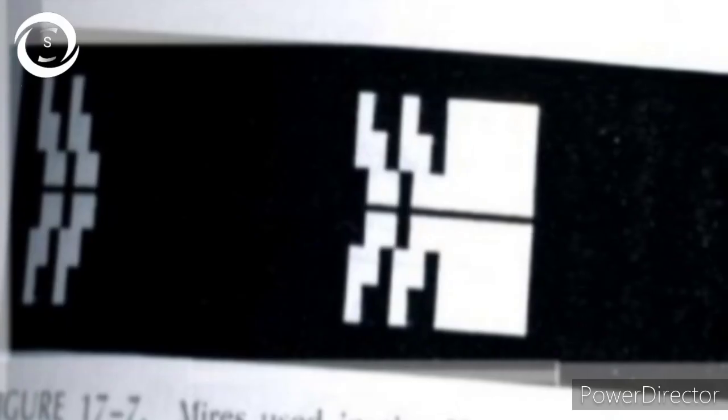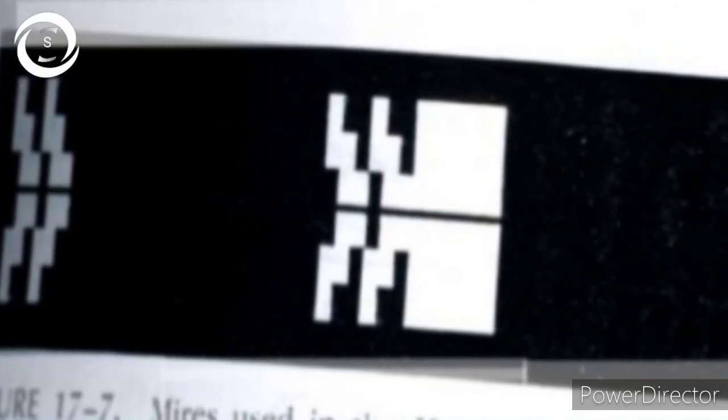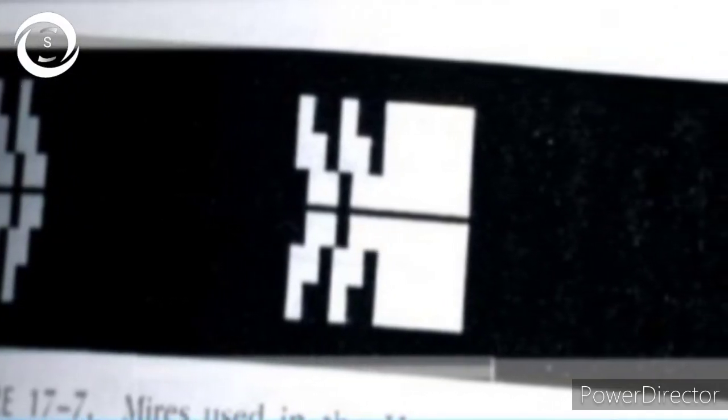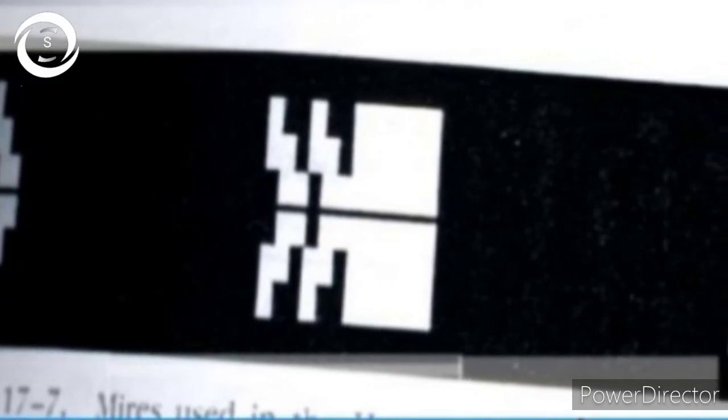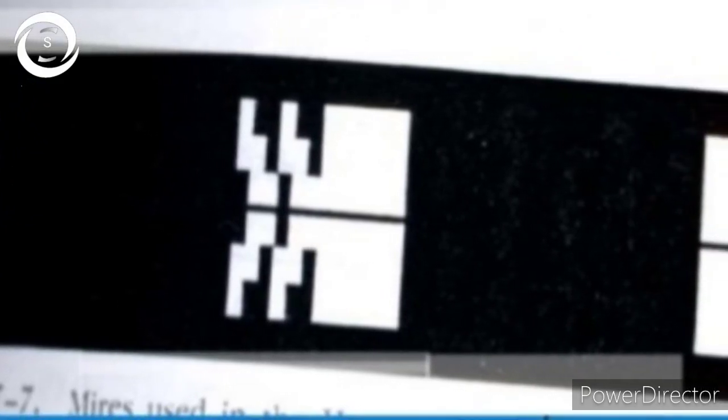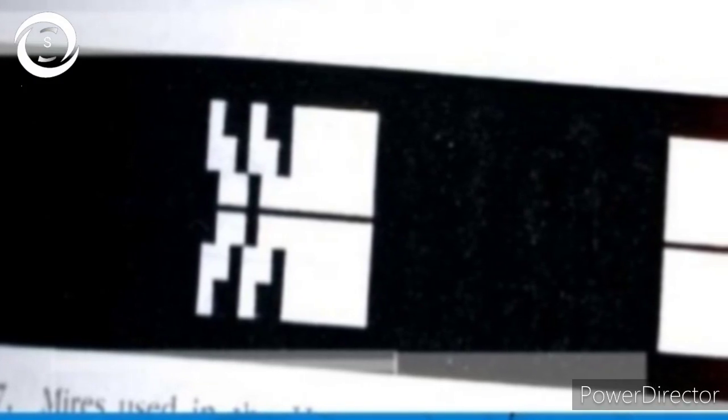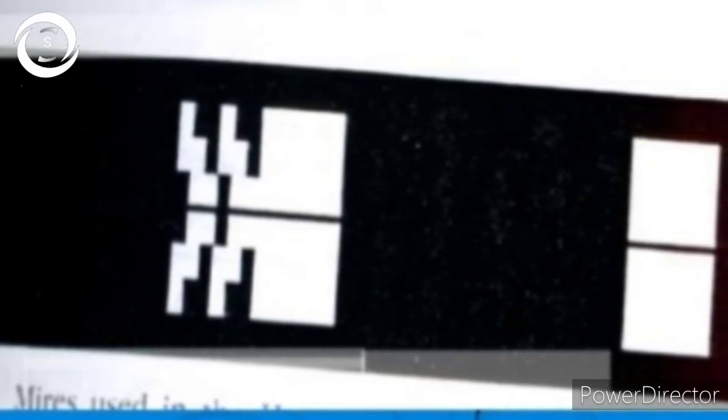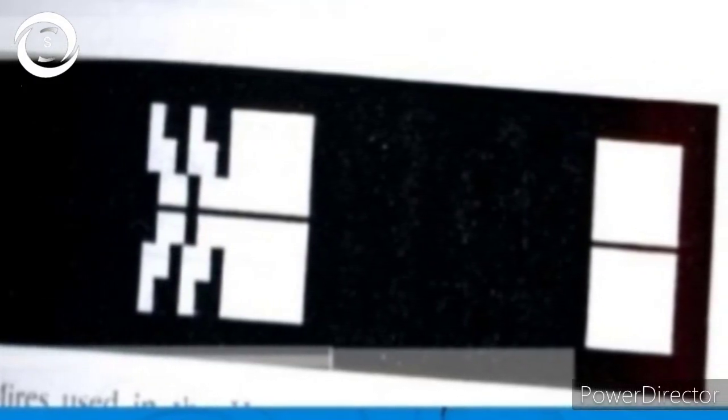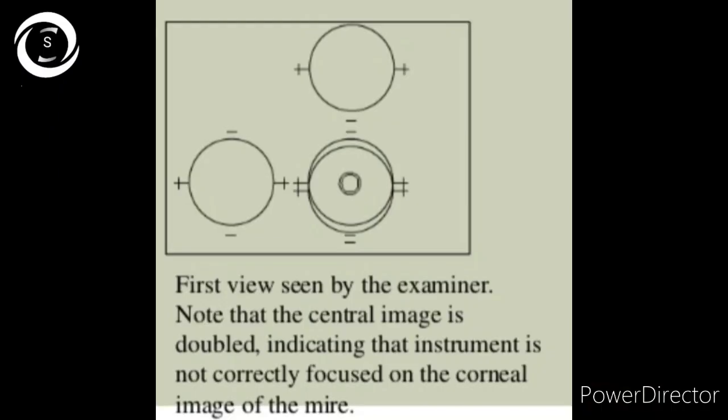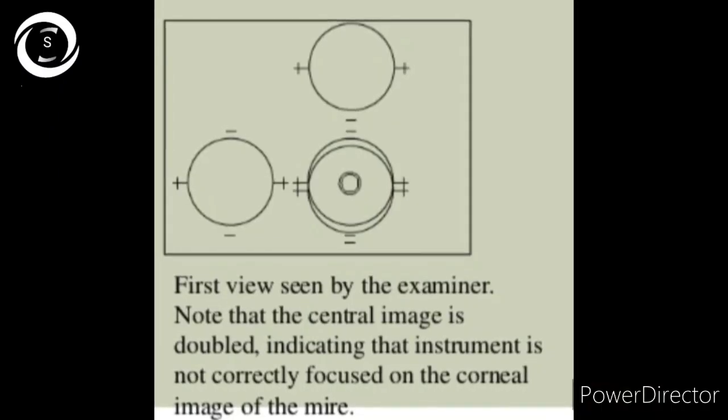Whereas in Javal-Schiotz, we have to obtain readings of both meridians separately. We have manual keratometers like Javal-Schiotz and Bausch and Lomb, as well as auto keratometers that are standalone or incorporated in other topographic machines.